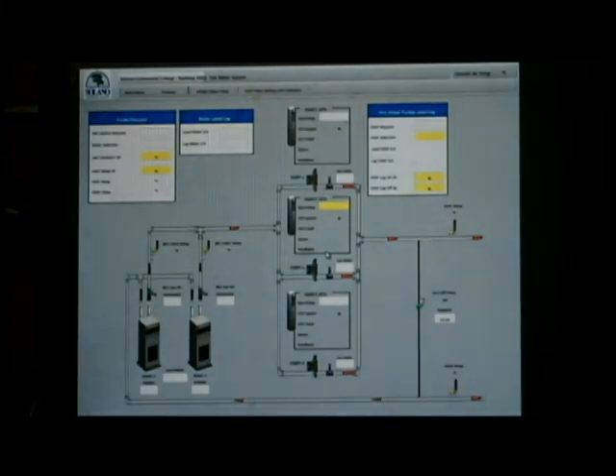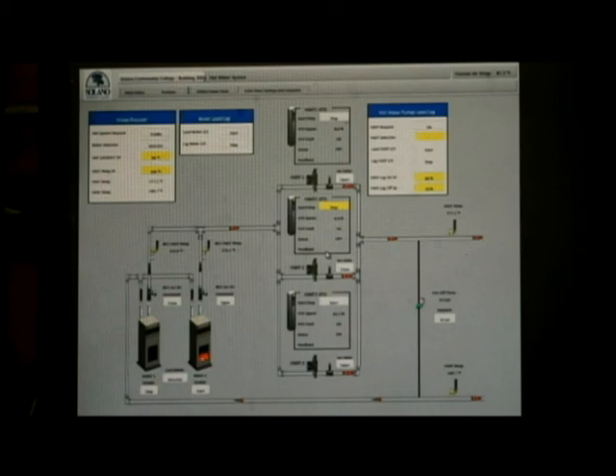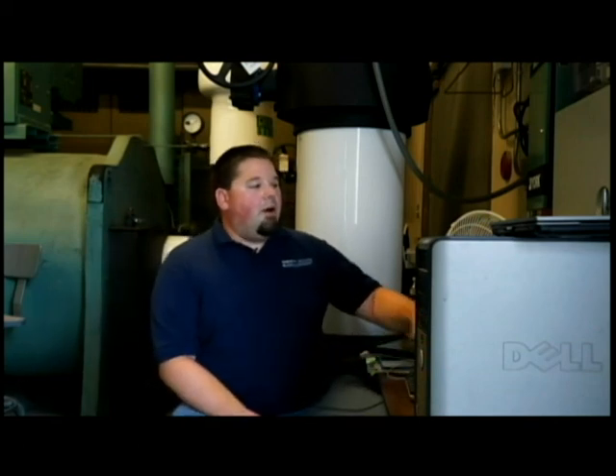On the flip side, there's also the hot water system here in the plant, and it's very similar to the chilled water system as far as sequence operates. A building goes occupied out on the campus. The zones, the reheat zones down in the building, request hot water. That in turn triggers the pump locally at each building, and that will then send a flag over here to the boiler or hot water plant. Once that flag comes over, just like over on the chill water side, our hot water pumps will start.